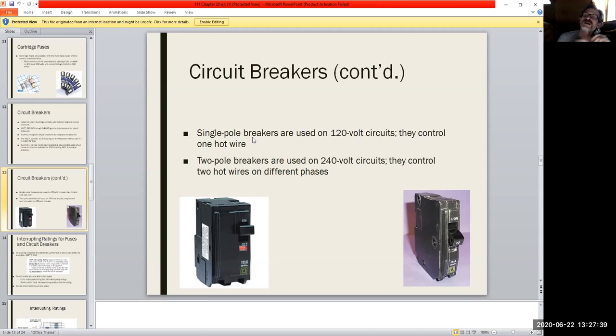Now, in the areas where I've got my workhorses, where I'm going to have motors and things like that involved, I'm going to have a 240 volt line involved. Well, that's known as a two-pole breaker, which means I'm going to have both hots going onto it. And you can see, if we compare, the one on the right is a single pole breaker meant for one line coming in, compared to this big boy on the left, which is meant to handle two lines going into it.